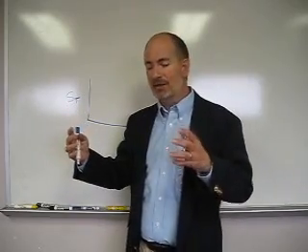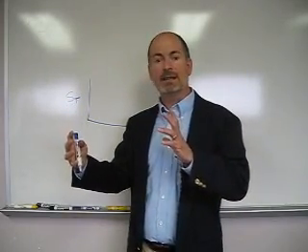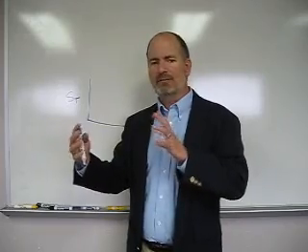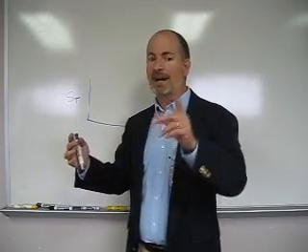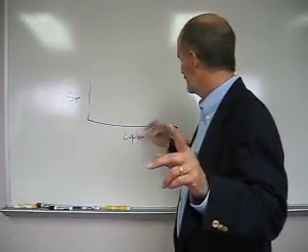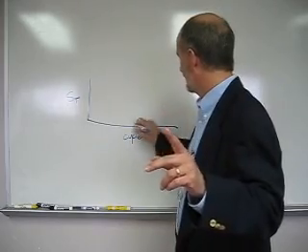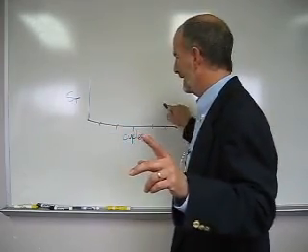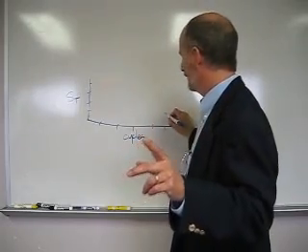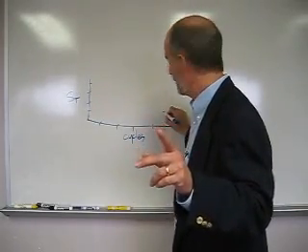So, if you had this bellows, and say you're going to only cycle a little bit, so you get lots of cycles, and you do that, and eventually it develops a fatigue crack. Now I know how many cycles that it failed at, and then that corresponds with a stress range over here, so I've got a data point.